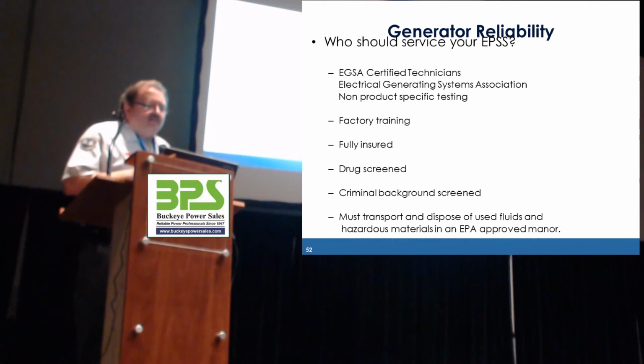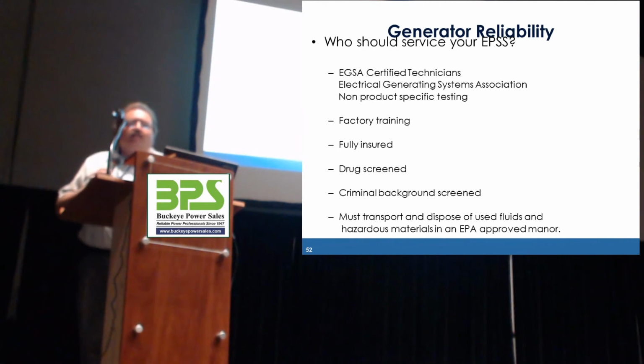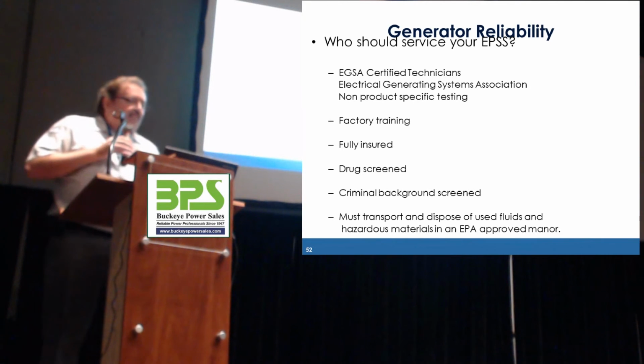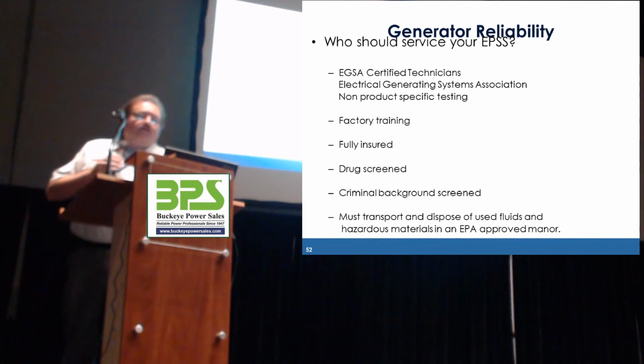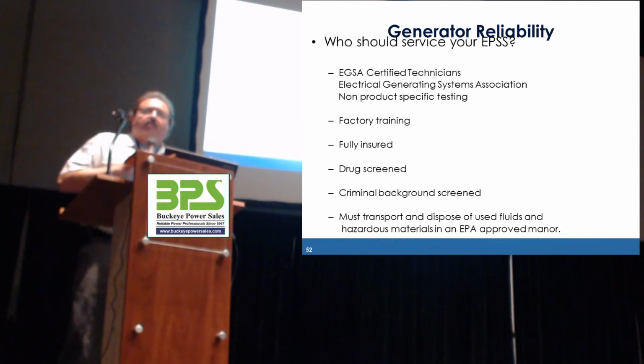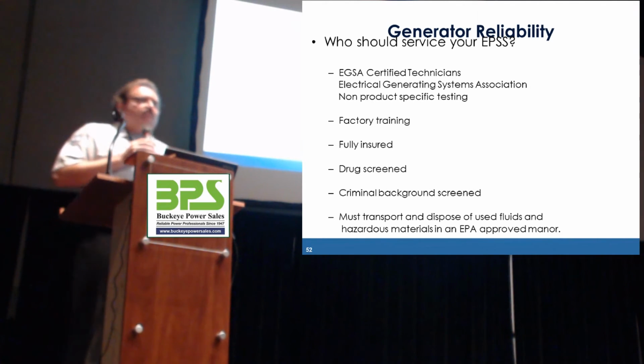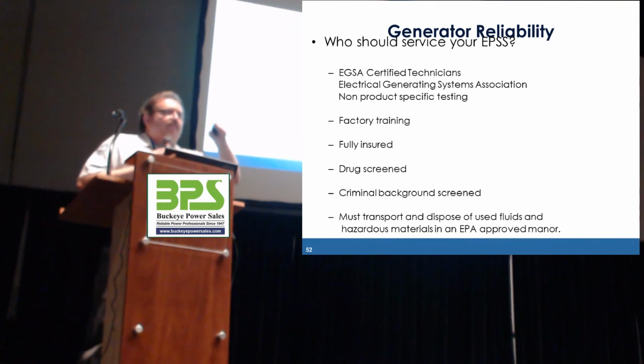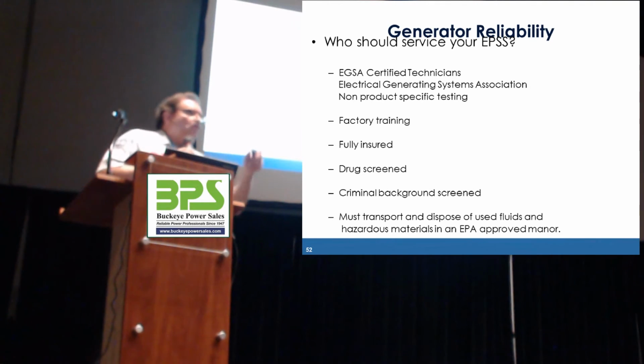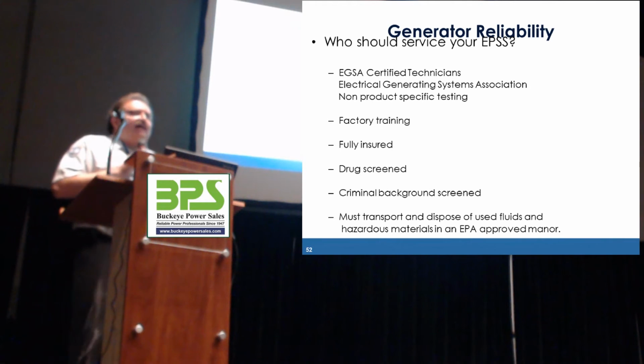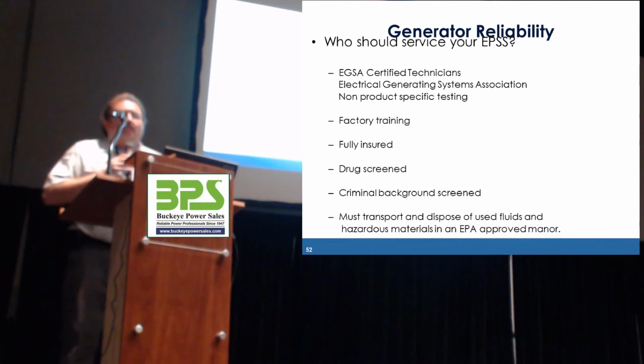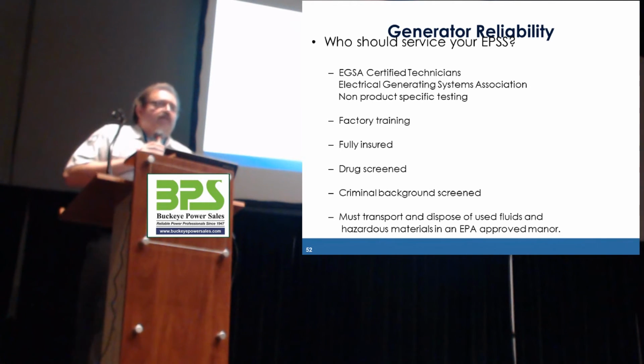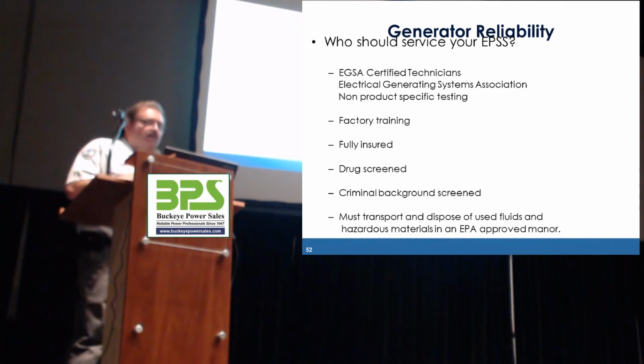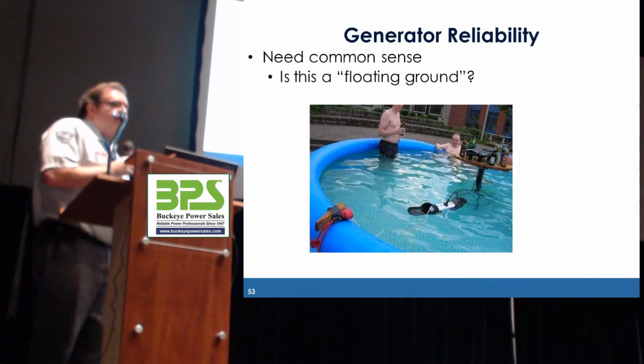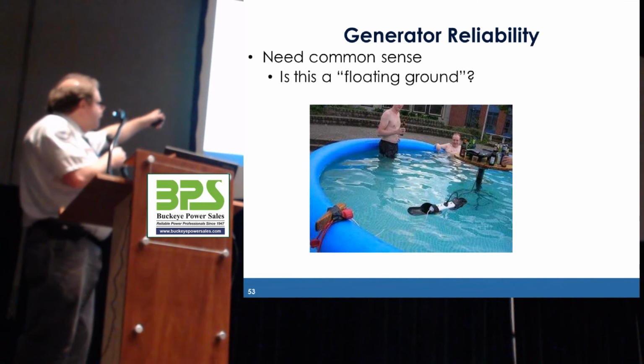Obviously, you want them to be fully insured, drug screened, background checked, and they must transport and dispose of used fluids and hazardous material in an approved way. Because as the owner, technically you're responsible for that, whatever, that battery that came out of the generator, the oil that came out of the generator, and if your guy takes it and dumps it on the side of the road, it's your responsibility. So you want to make sure that your folks are doing things properly. And then they need to have some common sense.